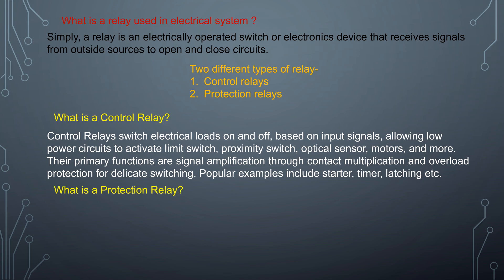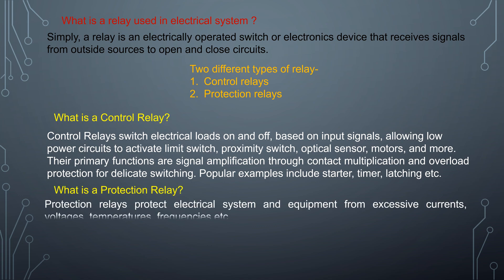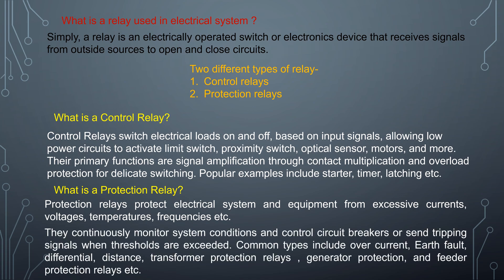What is a protection relay? Protection relays protect electrical systems and equipment from excessive currents, voltage, temperature, frequencies, etc. They continuously monitor system conditions and control circuit breakers or send tripping signals when thresholds are exceeded.